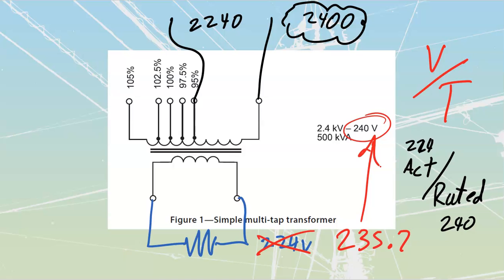Now, there is a reason that you do need to understand what the transformer taps are, because this was working off of the assumption that we started at 100% tap. There are some problems sometimes where we could be starting at the 102.5% tap. And if we're starting at the 102.5% tap, we can't necessarily work off of this. Once again, the most common thing that you're going to run into is that when you install a transformer, you put it on the 100% tap right away, because that's what the system is designed for. So usually when you come into these situations, you're dealing with that 100% tap and then having to change over to your values of voltage.